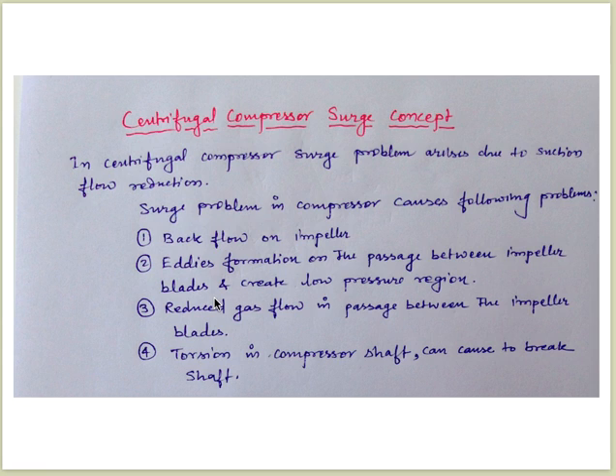Third, reduced gas flow in the passage between the impeller blades. Fourth, torsion in the compressor shaft, which can cause the shaft to break, because the backflow will try to rotate the compressor impeller in a different direction compared to the prime mover — such as an electric motor — which tries to rotate the compressor in the opposite direction. This torsion may cause the shaft to break.